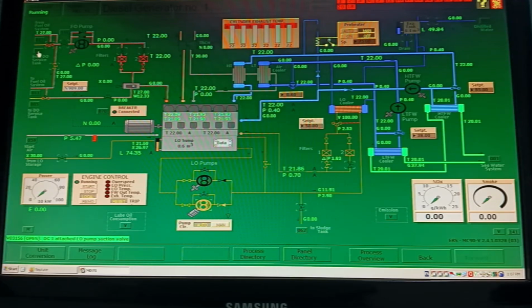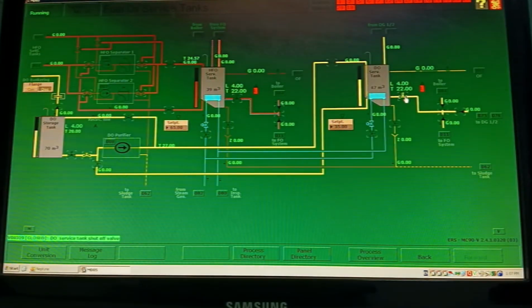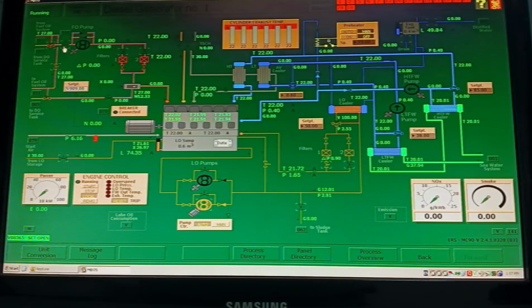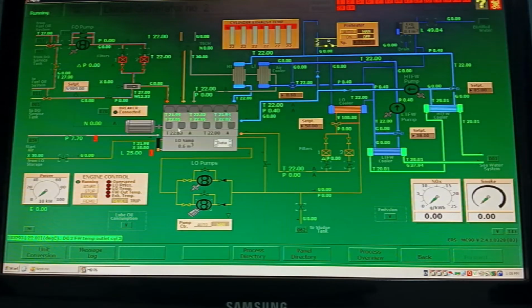And then go to your diesel oil service tank and open the outlets to both DG1 and 2. Open the valves, any one filter, your fuel oil system is set up. So you just need to get the pressure up to 13 bar or above. So we can do the same procedures to diesel generator 2.